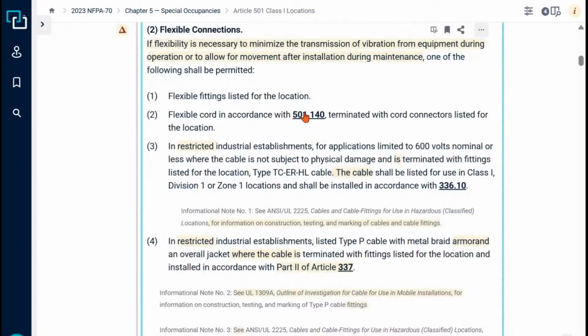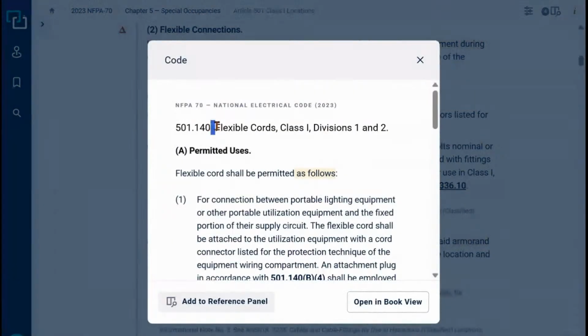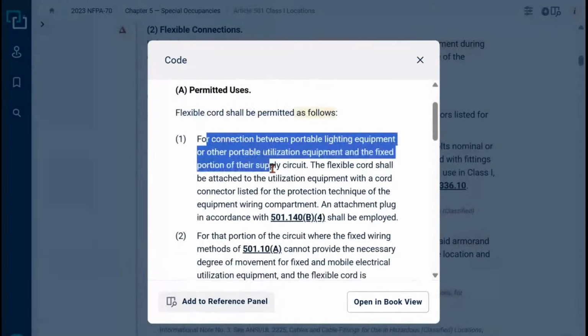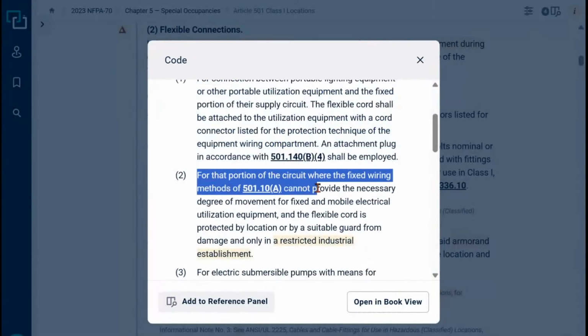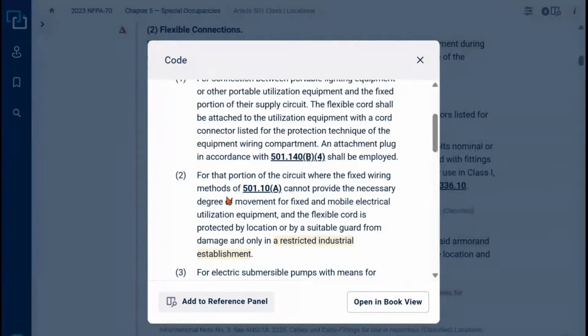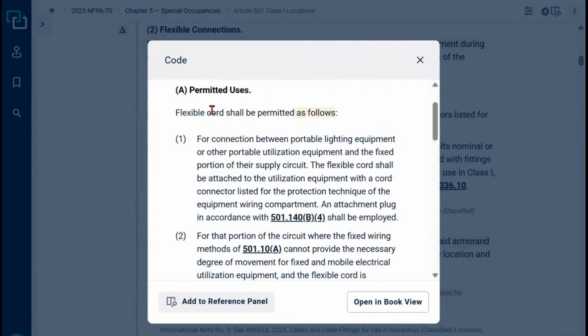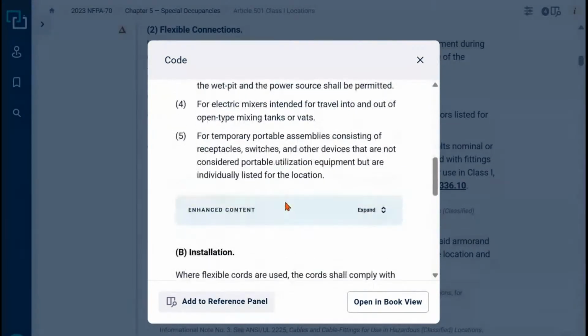But again, if you look at 501.140, you'll see flexible cords shall be permitted in the following, as long as you meet these conditions. That portion from the fixed wiring method cannot provide the necessary degree of movement for fixed or mobile electrical utilization equipment, and the flexible cord is protected by location or by a suitable guard from damage, and only in a restricted industrial establishment. So you have some allowances here for use in cord applications.